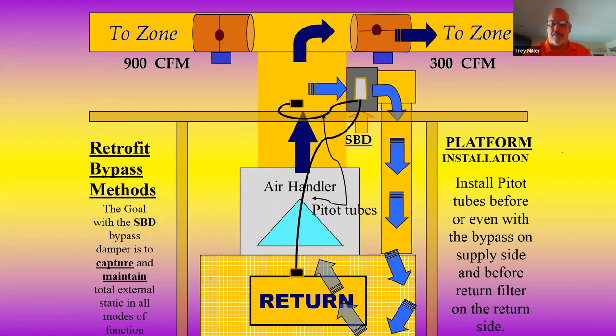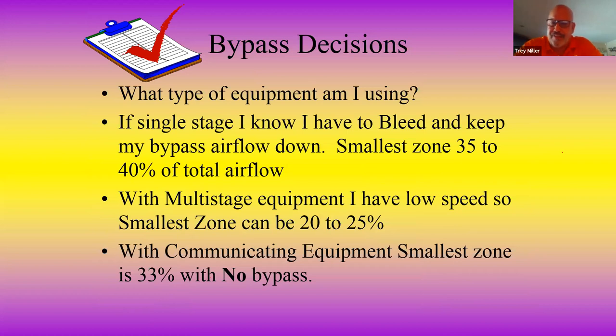Now, guys, the most important slide of the day is here. Bypass decisions. Guys, you've got to ask yourself, please don't try to beat this, because if you do, you'll probably lose. But if you follow these guidelines, you should not have problems with the system. What type of equipment am I using? If I'm using single stage, I know I have to bleed to keep my bypass airflow down. Smallest zone is 35 to 40% of the total airflow. Gentlemen, that's not a 6-inch run. It's not an 8-inch run unless you're on a really small system. 35 to 40%. And if your zone is smaller than that, we're going to have to bleed to get to that 35% to make sure we don't flood the bypass, create sweating, and create problems.